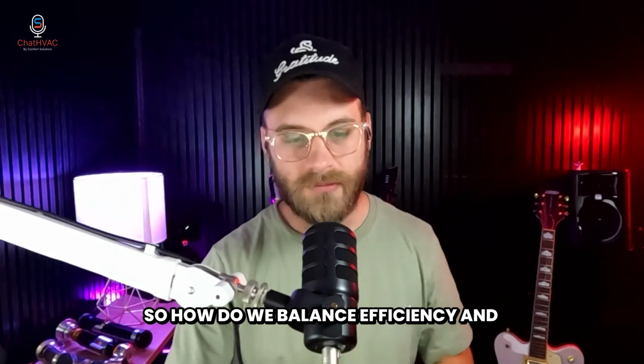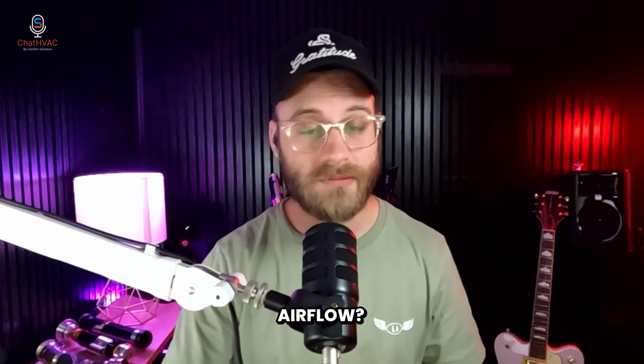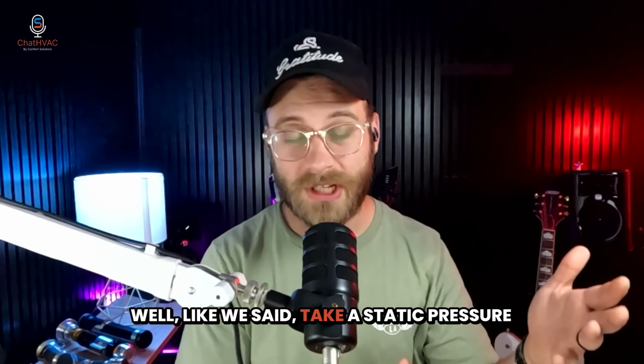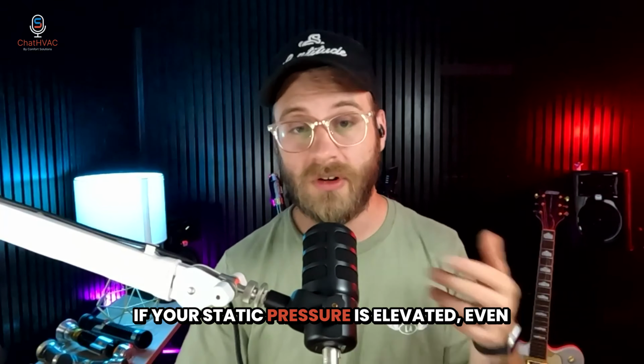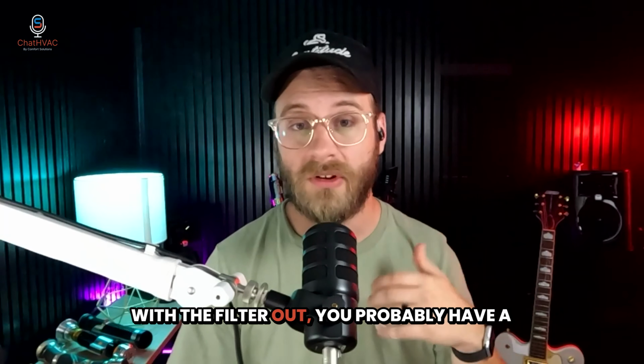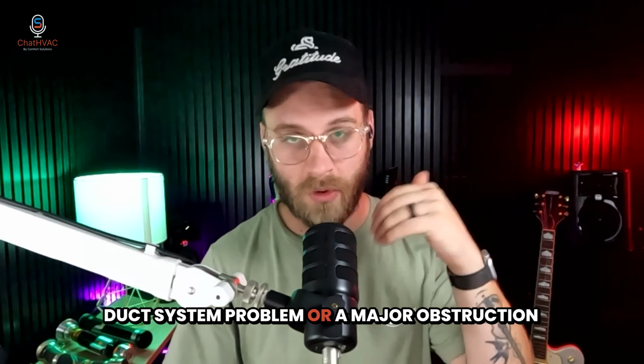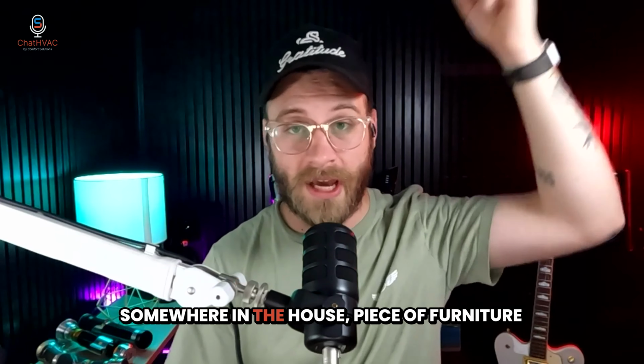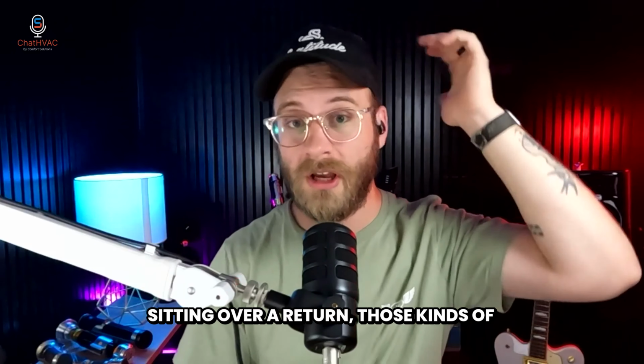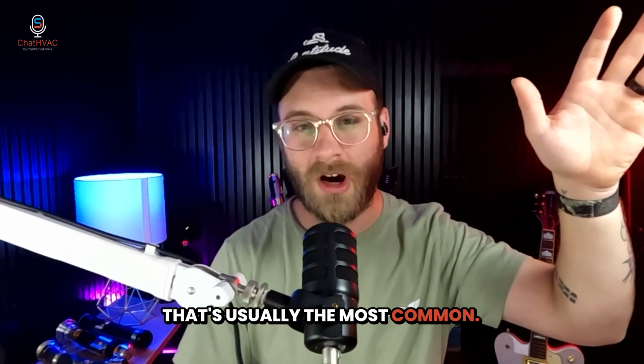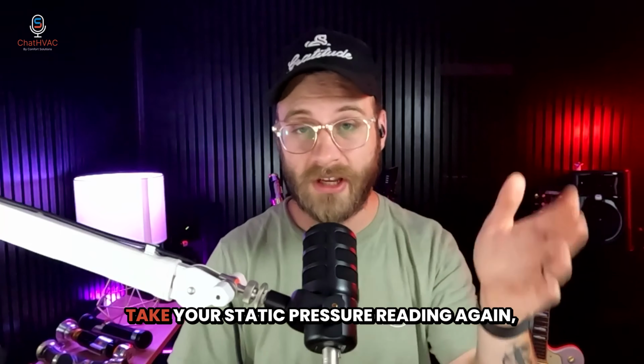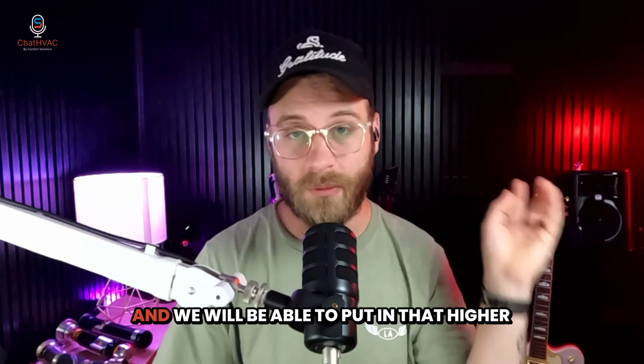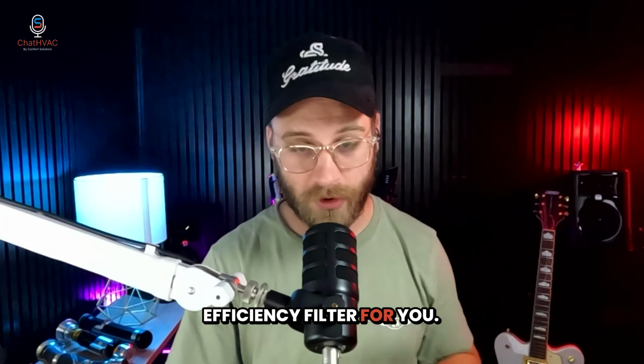So how do we balance efficiency and airflow? Well, like we said, take a static pressure reading. If your static pressure is elevated, even with the filter out, you probably have a duct system problem or a major obstruction somewhere in the house, a piece of furniture sitting over a return, those kinds of things. That's usually the most common. We'll go ahead and address that, take your static pressure reading again, and we will be able to put in that higher efficiency filter for you.